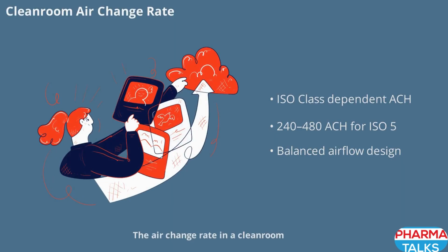Air change rate in a cleanroom is a critical parameter for maintaining cleanliness. For ISO Class 5 cleanrooms, air change rates typically range from 240 to 480 air changes per hour, ACH. This high rate ensures that particles are rapidly removed from the environment, maintaining strict particle control. Achieving the right balance in airflow design is essential for both cleanliness and energy efficiency.